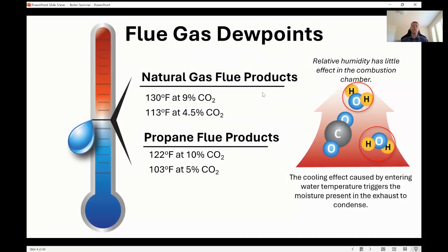Of course, your type of combustion will vary how much CO2 you have in the stack. So an atmospheric boiler, some of us of a certain vintage can remember them. An atmospheric boiler won't have fans that control that fuel to air ratio. What they'll have is just a burner and Mother Nature, whatever the room provides for air. And a lot of times those will be less efficient combustion. So basically an atmospheric product in natural gas will have a percentage in the stack of roughly about 4.5% CO2. And that in turn comes to about 113 degrees Fahrenheit.